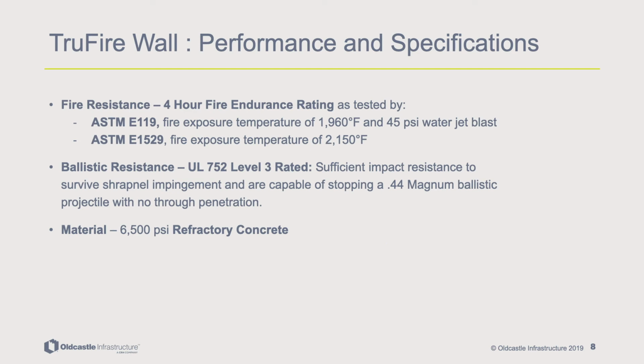Oldcastle's TruFire wall has been tested at fire exposure temperatures of 1,960 degrees Fahrenheit and 2,150 degrees Fahrenheit with a 45 psi water jet blast. It received a 4-hour fire endurance rating. TruFire walls maintain a UL 752 Level 3 rated ballistic resistance. These walls can withstand sufficient impact resistance to survive shrapnel impingement and are capable of stopping a .44 Magnum ballistic projectile with no through penetration. These walls are constructed using 6,500 psi refractory concrete.